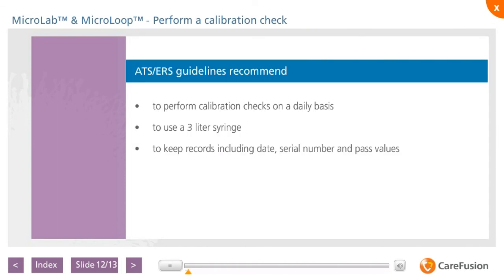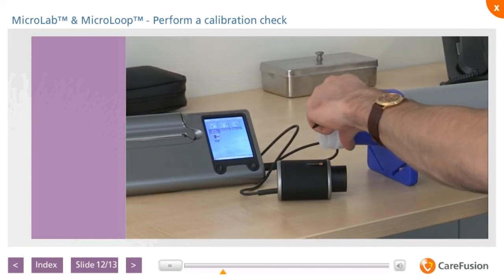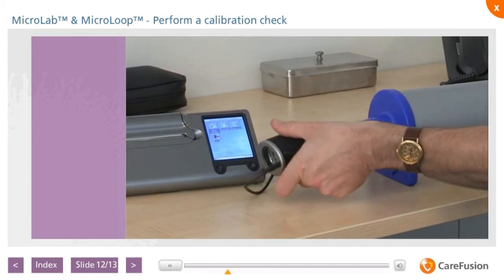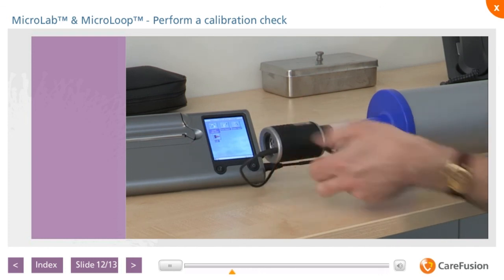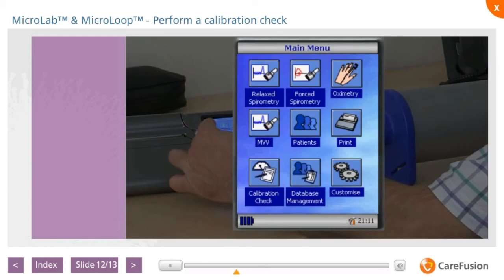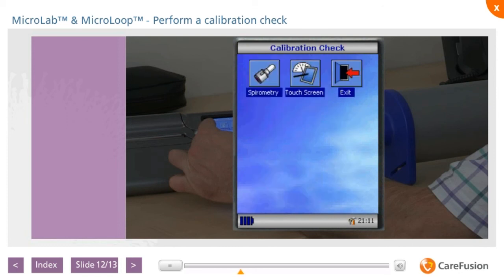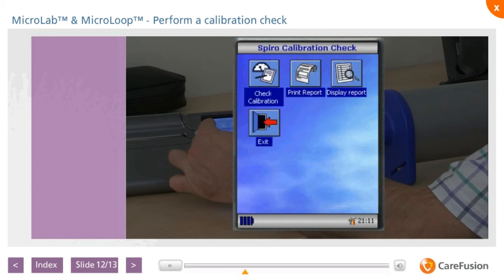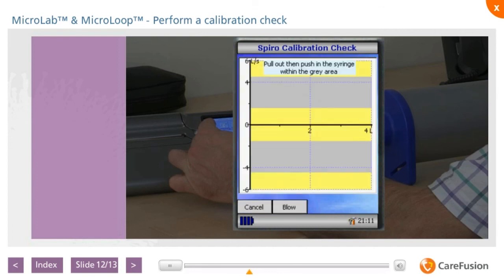The current ATS-ERS guidelines recommend that spirometry calibration checks are performed on a daily basis, using a 3-litre syringe. It's important that records are kept of calibration checks performed on the spirometer, including the date, spirometer serial number, and the pass value. Connect the syringe adapter to the syringe and connect the spirometer transducer as shown in the picture. Touch the calibration check icon on the main screen of the spirometer. Select the spirometry icon and then select Check Calibration.